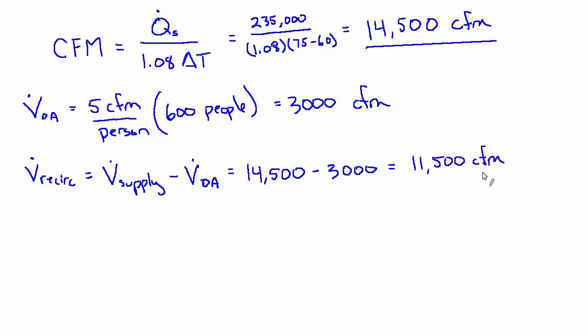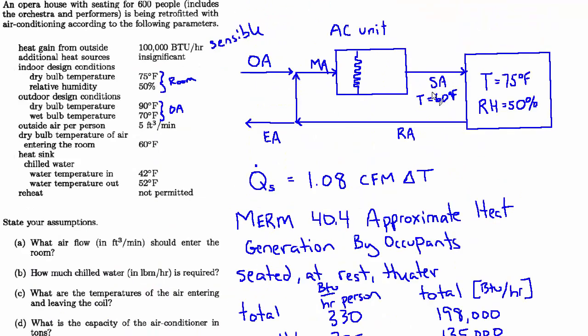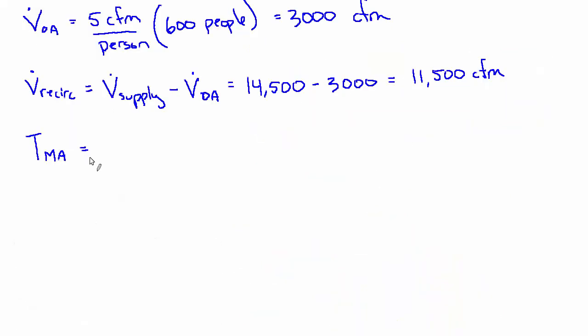And now we can do that mixed air calculation. So our goal is to find out what's the resulting temperature of these two airstreams of known temperatures and known volumes mixing together.